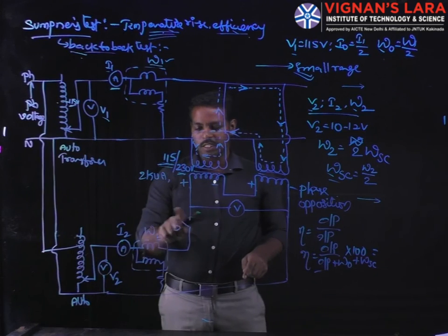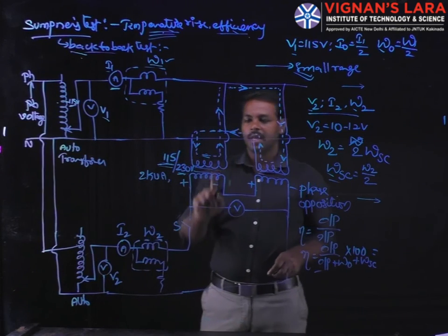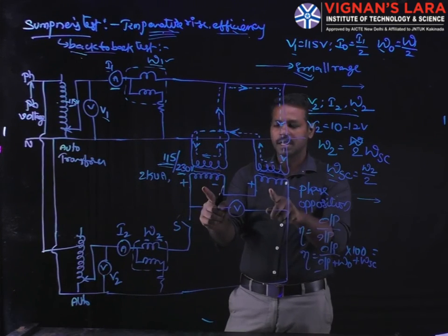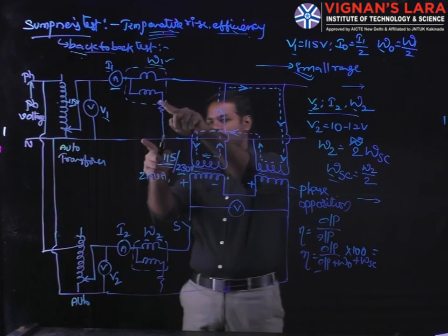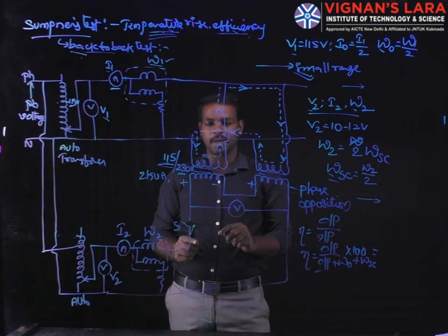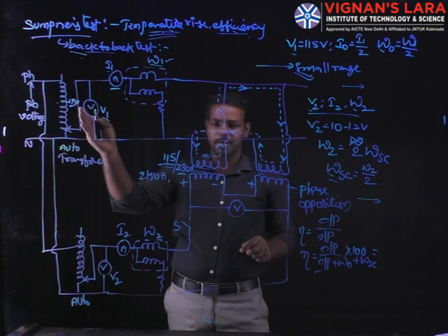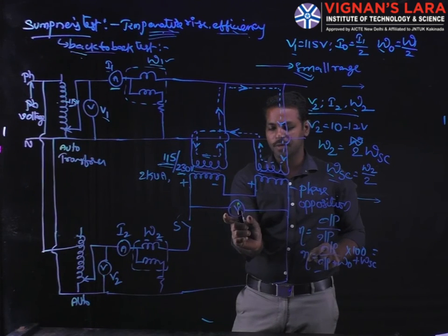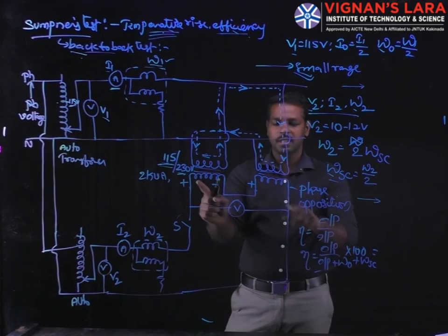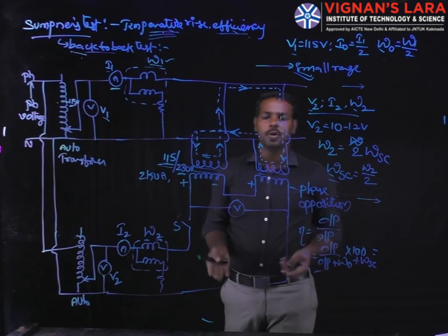Initially the switch is open circuited. These two are connected in series and phase opposition, and these two are connected in parallel across the supply. By applying the autotransformer with rated voltage to the LV windings, the voltmeter reads 0, just like an open circuit.